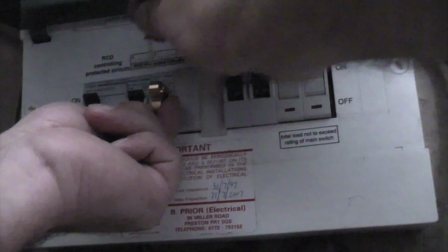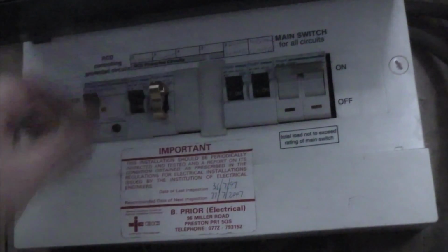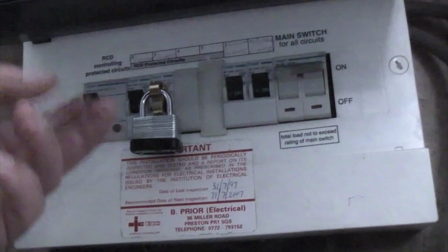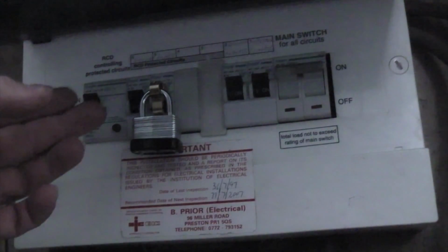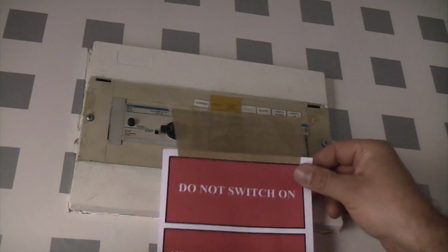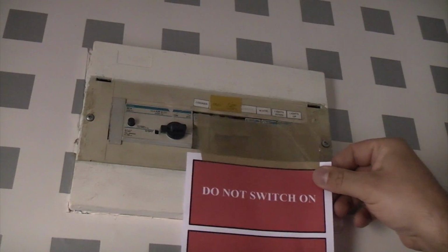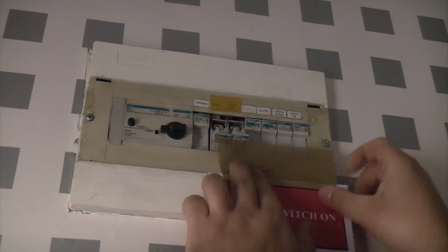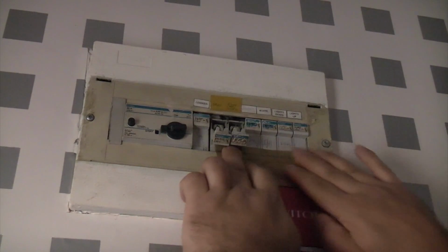So we'll just slide that over there. Then we'll just tighten up the grub screw. And now that's nice and tight on there, we can now put a padlock through there and lock that. And that'll prevent anybody from switching that circuit breaker back on. We're going to stick a label on there saying do not switch on because we're working on the circuit as an extra precaution.